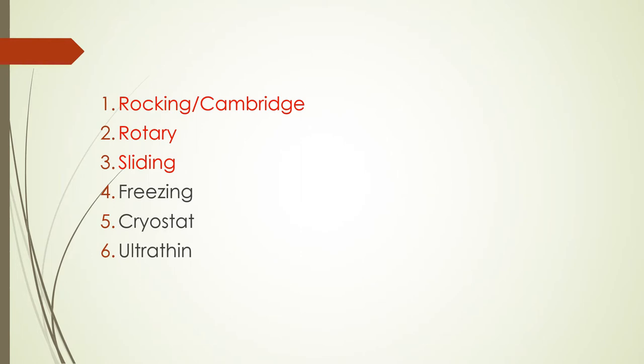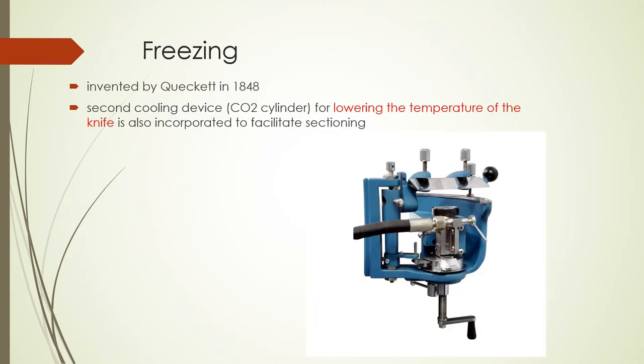Next we have the freezing microtome. It was invented by Queckett in 1848. As the name suggests, it involves a secondary cooling device — usually a carbon dioxide cylinder — for lowering the temperature of the knife. Take note of the phrase 'lowering the temperature of the knife,' because we're going to distinguish it from the cryostat, which we'll tackle now.